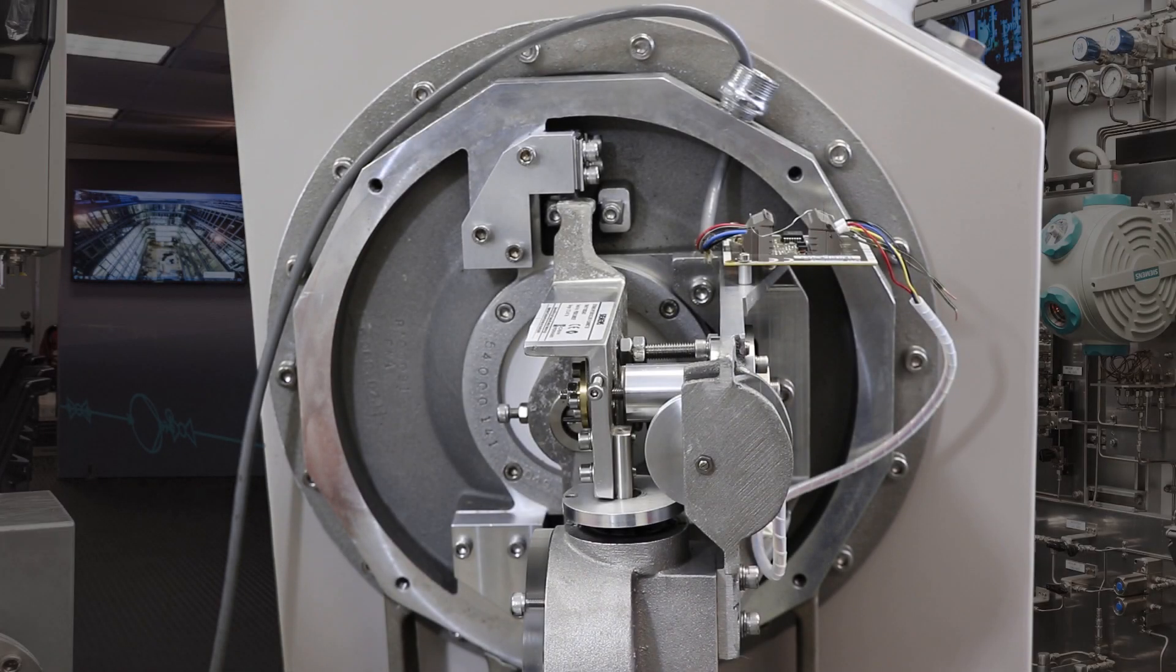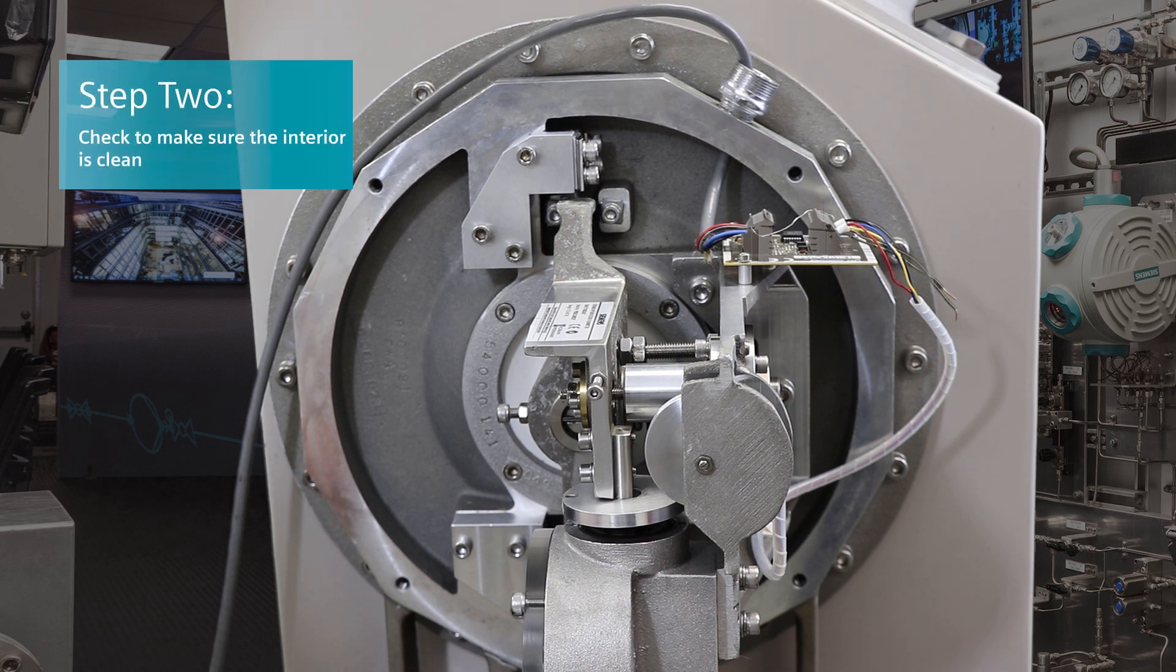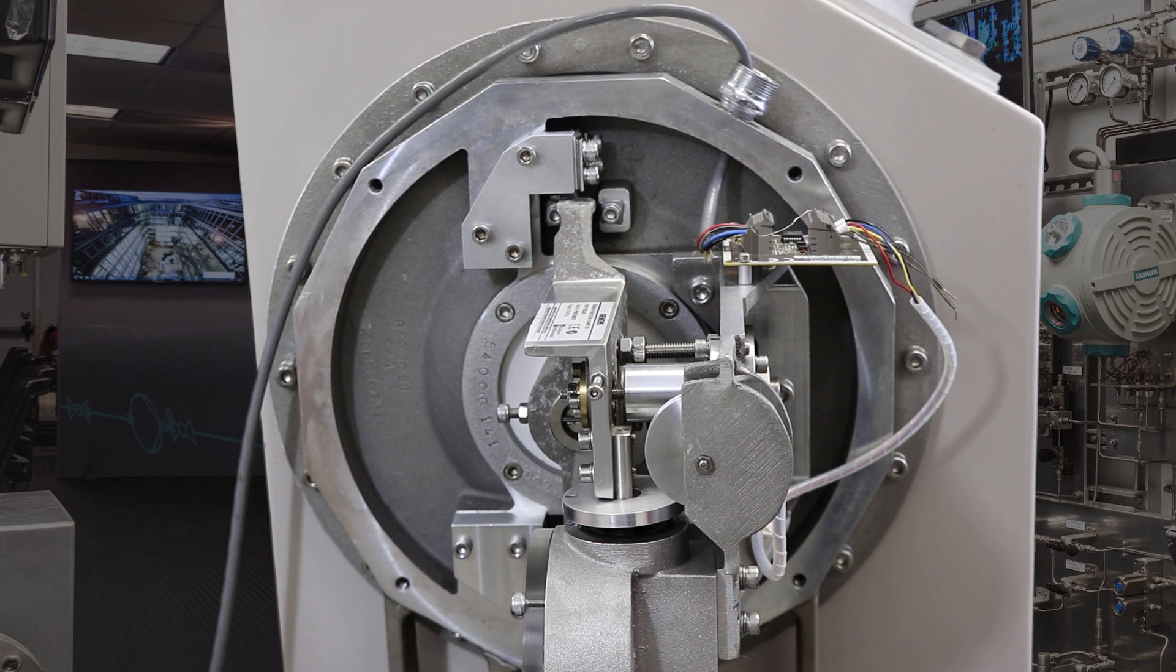After you inspect the sensing plate, you will go over to the sensing head and remove the cover. Check to make sure that the interior is clean at this time. If the interior is not clean and has product around it, it could mean that one of the gaskets is torn or bad.